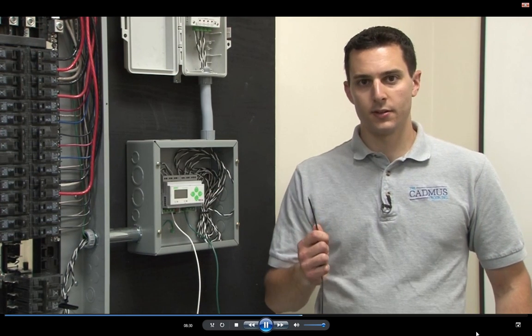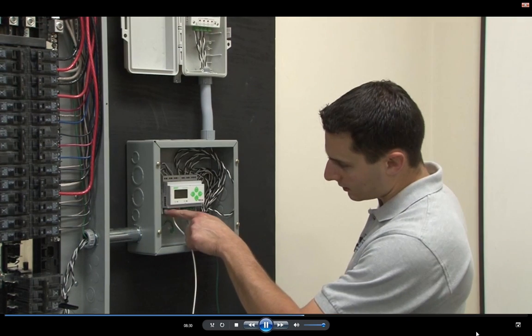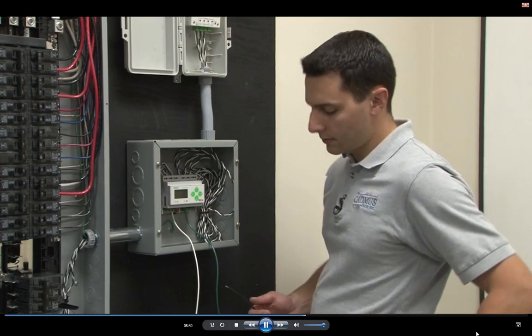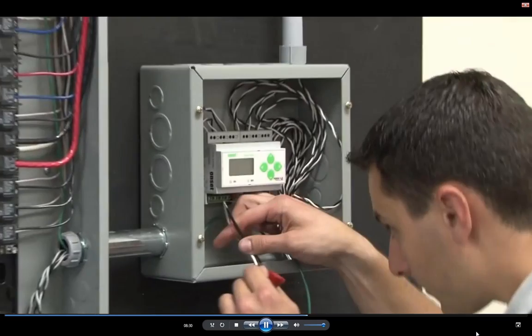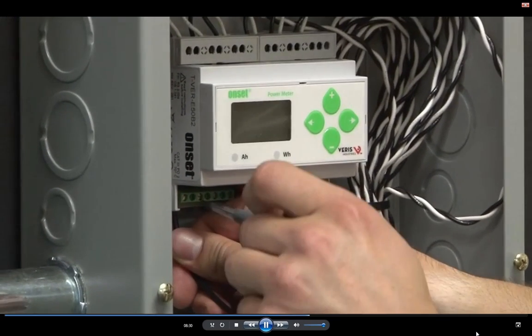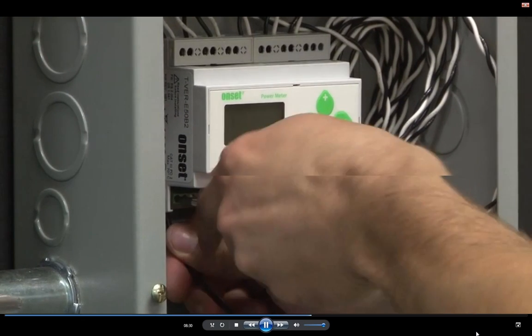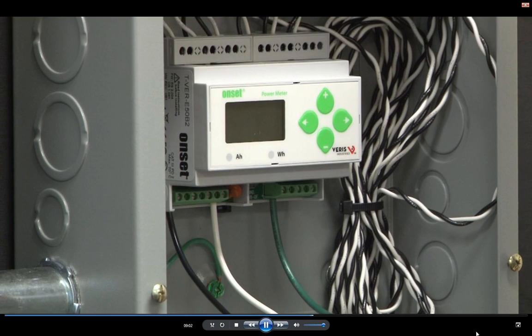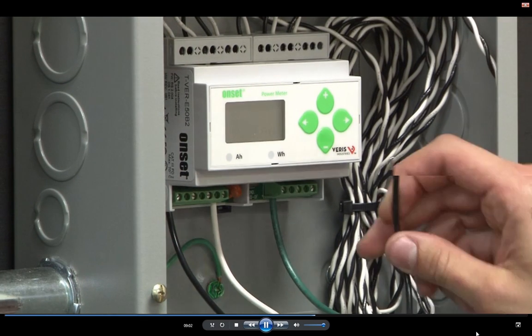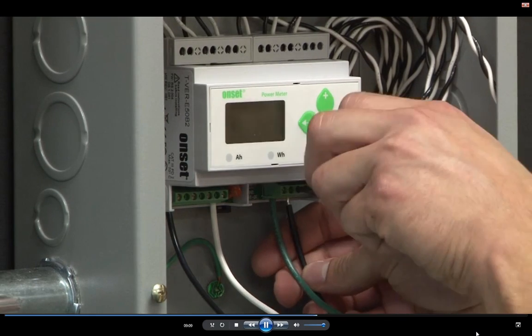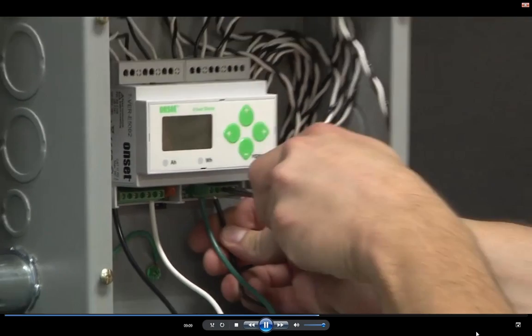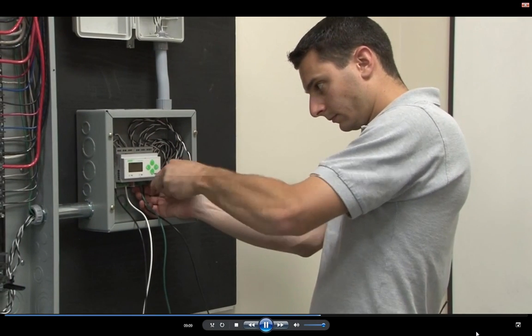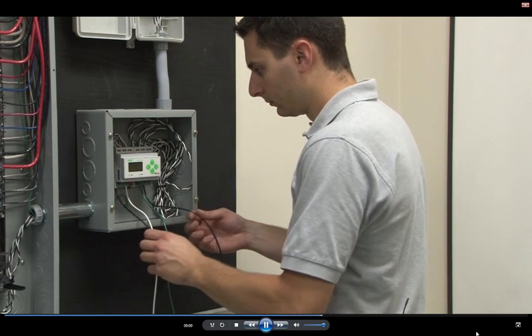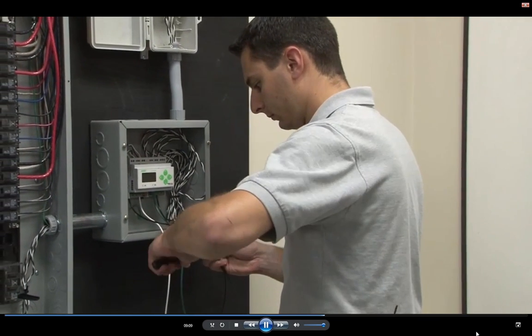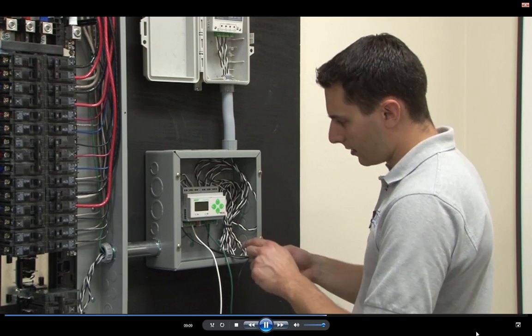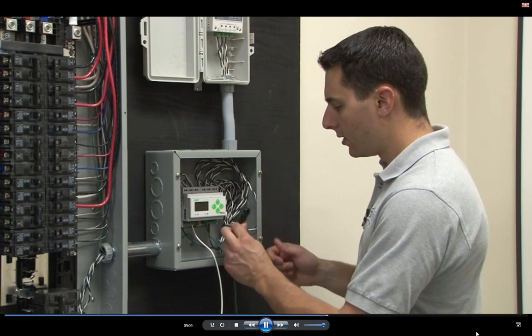We will now connect our black phase A terminal conductor to the far left phase A terminal, as well as terminal number 1 in our control power terminal block. So we bring the black phase A conductor together with the terminal 1 conductor on the control power using a listed terminal.